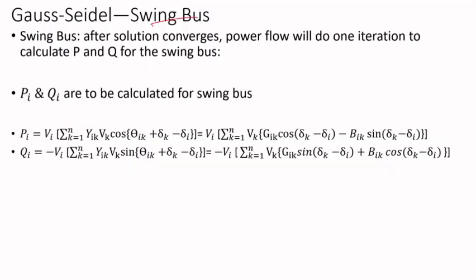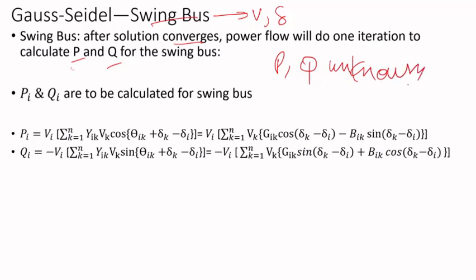For the swing bus, after the power flow solution converges for all buses, the program goes through one more iteration to calculate P and Q at the swing bus — because for the swing bus, voltage magnitude and angle are known but P and Q are unknown.